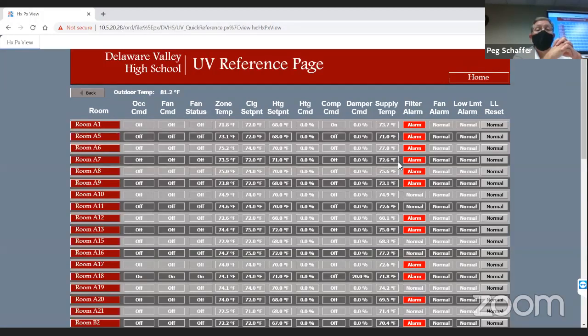Here we go. I said you might see some alarms here. Those guys changed the filters, so we need to go reset the alarms. That's kind of neat. We can alarm the system to say, hey, you've got to change your filter, and then they can get that alarm and reset it. So we need to go through and reset those alarms now that the filter has been changed. I'm just going to click on a unit ventilator.